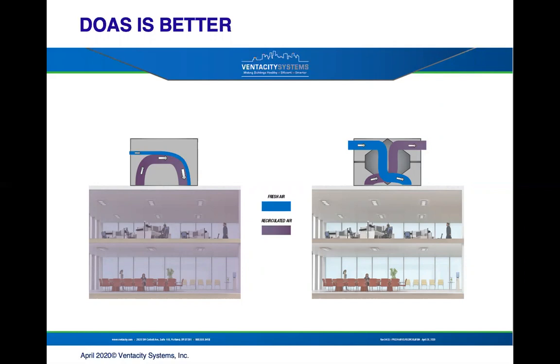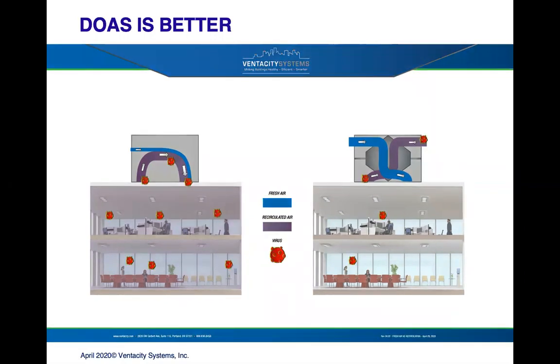From a perspective of ventilation with viruses, a virus in one section of the building on the left is going to be returned to the roof and recirculated. That air is reheated or cooled to meet the heating and cooling load of the building. The damper's opened, introducing some fresh air if that's called for, and then it distributes it back into all the building, or that entire zone that the rooftop unit is serving. As opposed to a dedicated outdoor air system with heat recovery, where you're doing exhaust directly from the space and directly to the outside, so you're not going to be spreading viruses in the building.